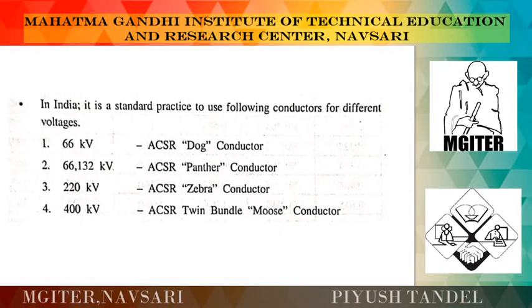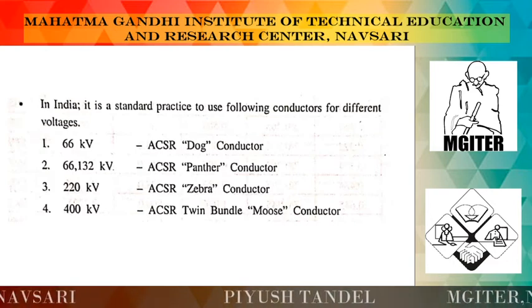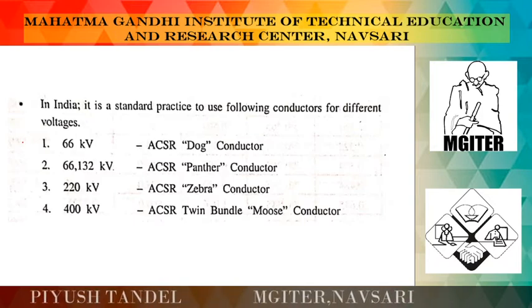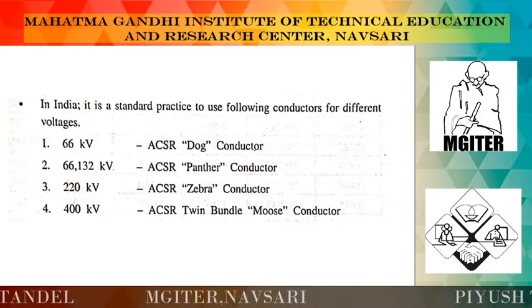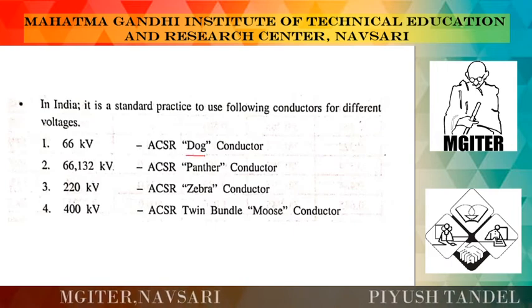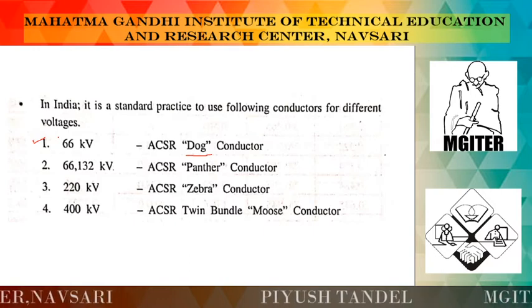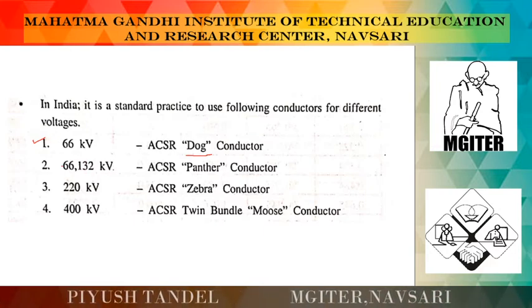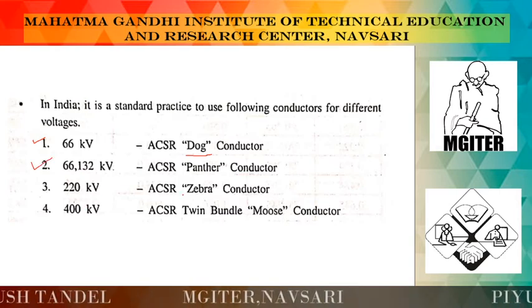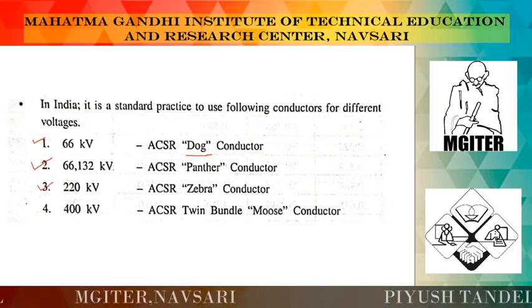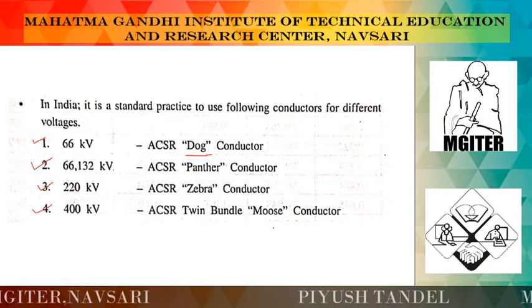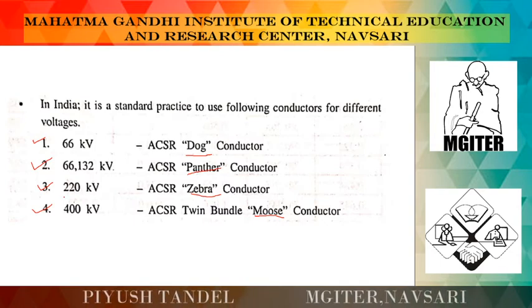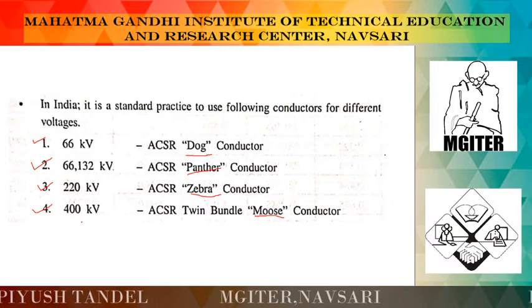Different types of conductors are used on transmission lines depending on the voltage class and amount of current. In India, it is standard practice to use ACSR conductors for different voltages. For 66 kV, we use the dog conductor; for 66 to 132 kV, we use the panther conductor; for 220 kV, we use the zebra conductor; and for 400 kV, we use ACSR twin moose conductor.